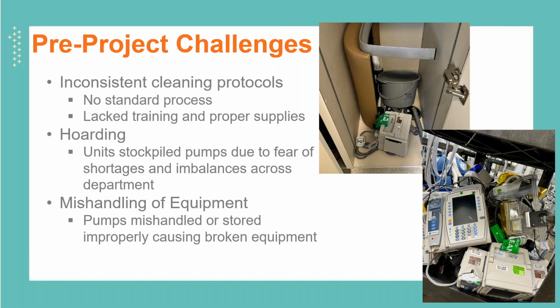So the other part: hoarding and inconsistent cleaning are related, and then there was the mishandling of equipment. The actual transport of equipment was not done properly, and so these devices were susceptible to more damage, being transported up and down elevators and corridors. We were actually seeing on our CMMS reports that up to 50% of our repair work orders for all medical equipment were due to physical damage related to pumps. And pumps only make up 20% of our fleet. So there was a clear imbalance.